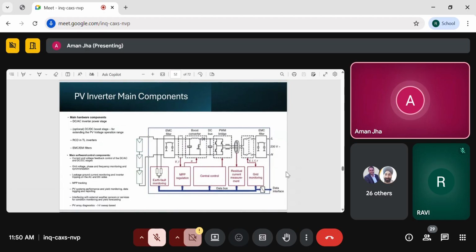So, if you divide this in terms of software and hardware, on the hardware side there is the DC to AC inverter power stage, RCD, and EMI/EMC filters. These three are the major blocks for the hardware engineers. For software perspectives, there are the feedback controls and embedded controls for the DC to AC and DC-DC stages, and grid synchronization, and then the leakage and ground current monitoring and their decision making. Whatever is there, you have to treat it.